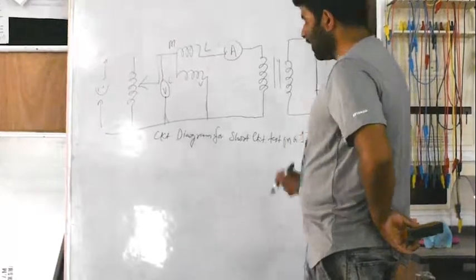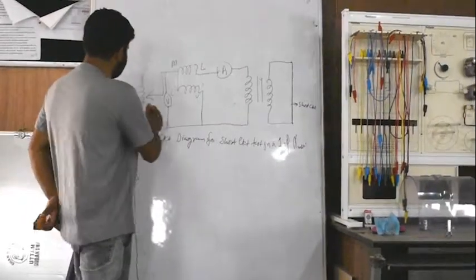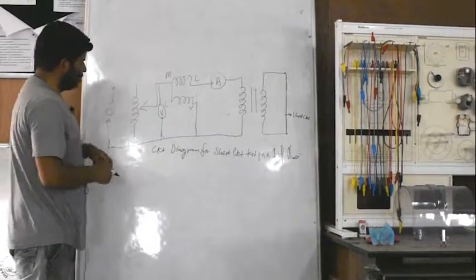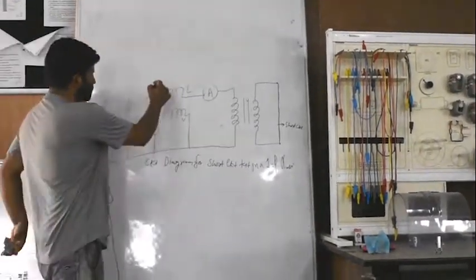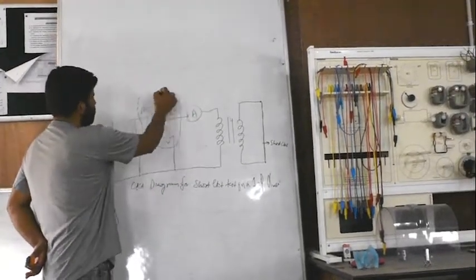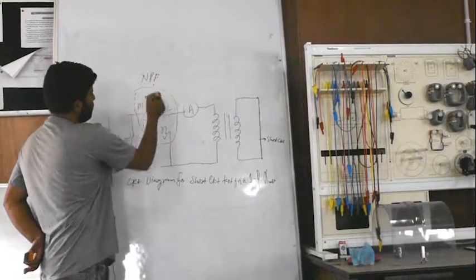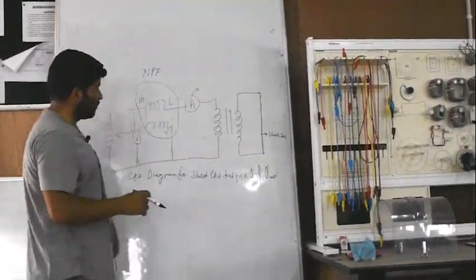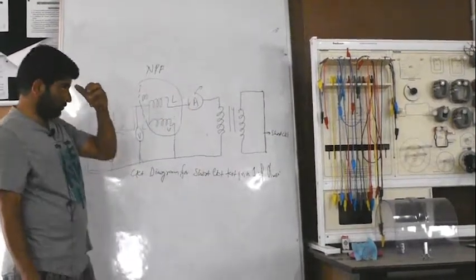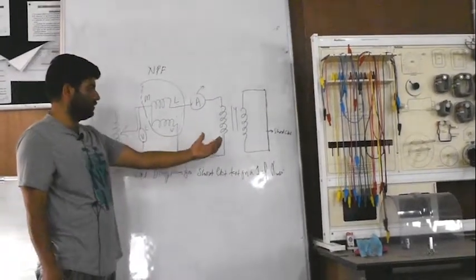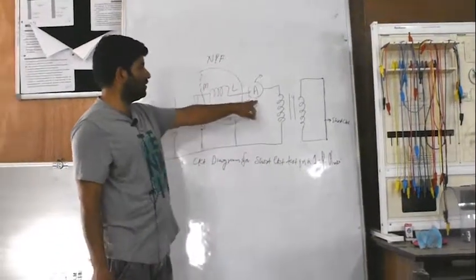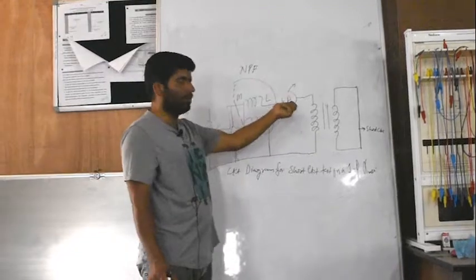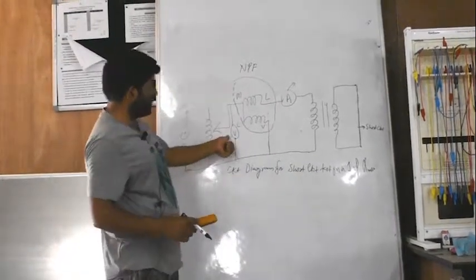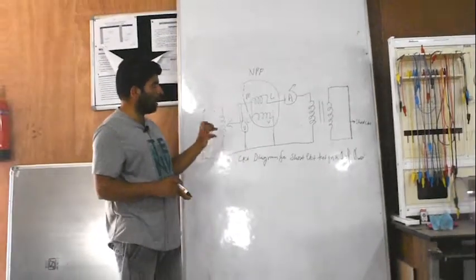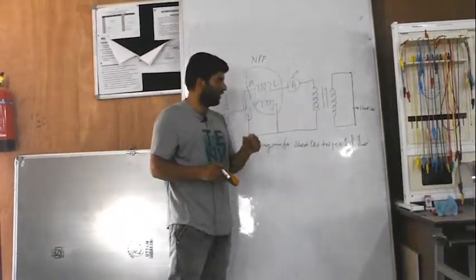Right, so in this, what we have done, we have connected a variable AC power supply. We have these three measuring instruments. This is the wattmeter, which will be a normal power factor wattmeter, NPF. For the ammeter, you should connect one of high range capacity, because we are performing the short circuit test, so its current carrying capacity must be higher than, or of the order of, the short circuit current. And we will be using a voltmeter to measure the voltage at which the short circuit current is flowing in the winding.